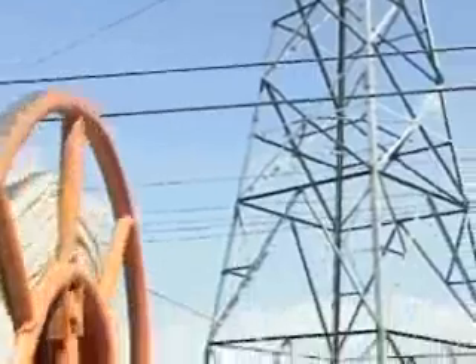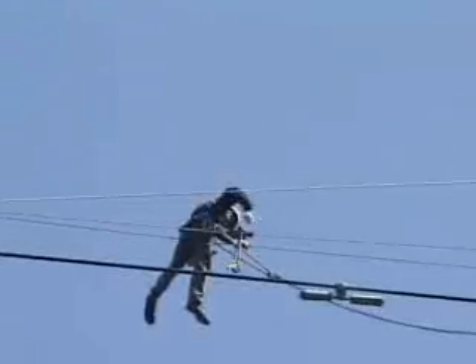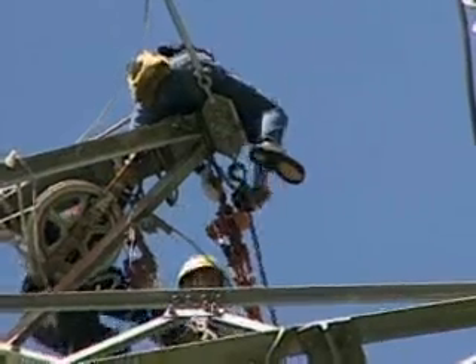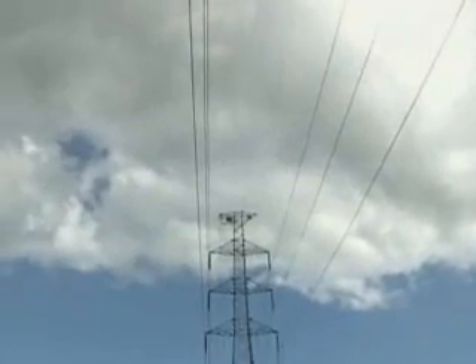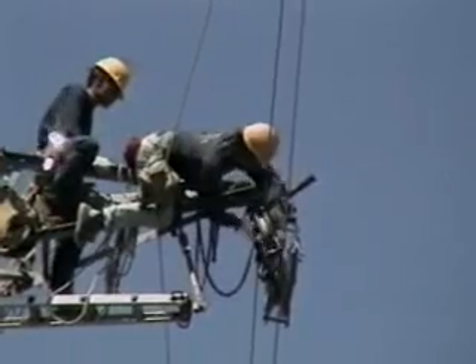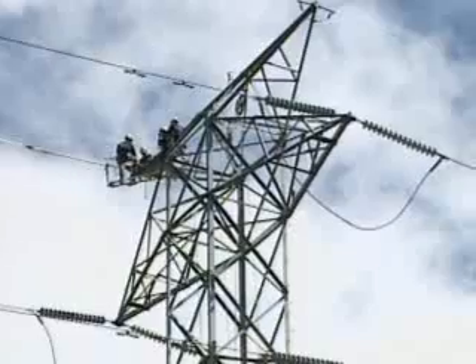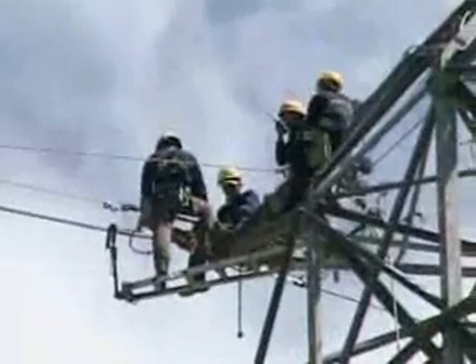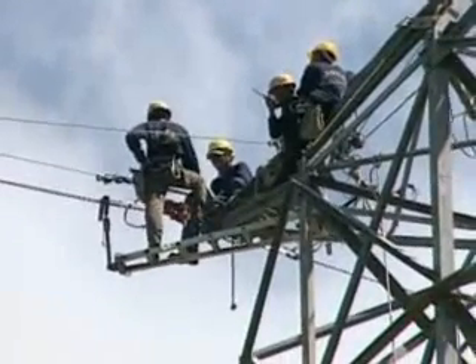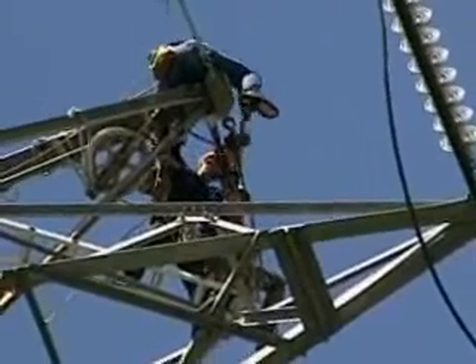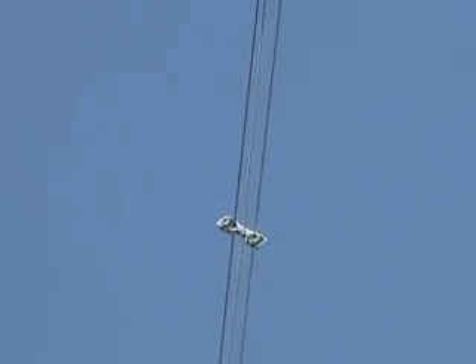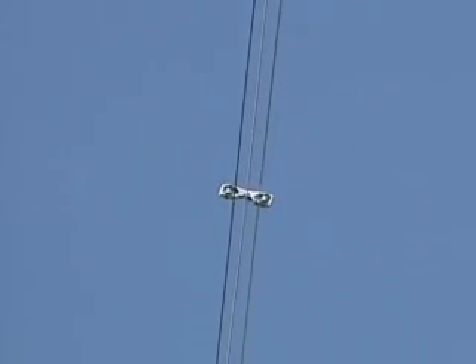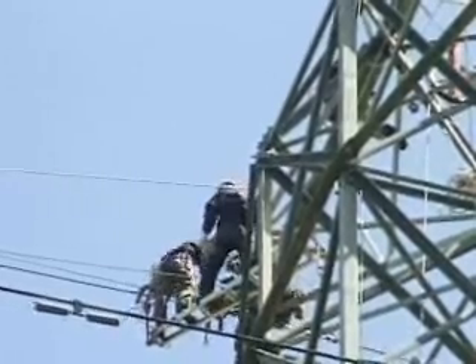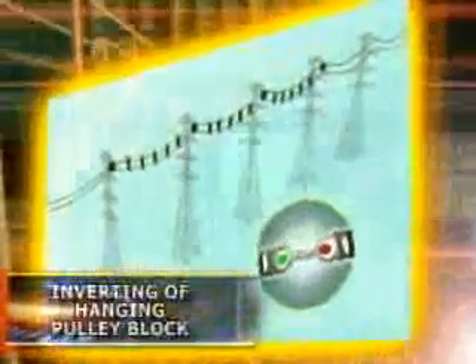Once the OPGW reaches the final tower in that drum section, it is anchored to the end tower with come-along and lever block. The existing ground wire at intermediate towers is then shifted by transferring its support from suspension or tension clamp to the pulley blocks. Likewise, the existing ground wire at both end towers is then re-anchored with come-along and lever block. The tension of the lever block on the OPGW is then increased until the sag of the OPGW reaches the same level with the existing ground wire. Then the tension of the lever block on the existing ground wire is decreased, forcing it to slack slowly. As this happens, the hanging pulley blocks through the wire, which are still threaded, will invert.